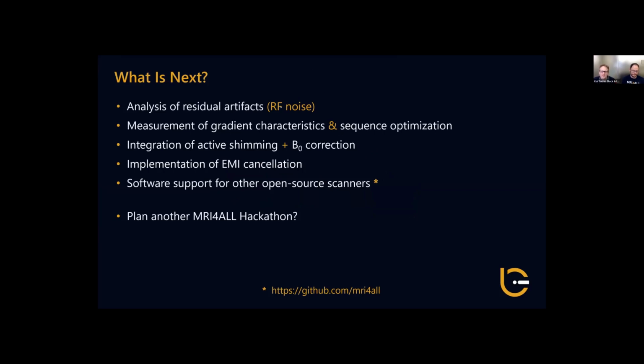We really haven't looked much into the system capabilities yet, so we haven't measured the gradient performance much, and there's definitely a lot of work that needs to be done on the sequence side. We also haven't tested the active shim array that Leo showed. That's definitely on our list. Another technical item is to integrate EMI cancellation, so basically noise cancellation. We have prepared the hardware for that, but we haven't implemented the algorithms yet. I think this could be very interesting because it would potentially allow using the scanner without an RF shield.